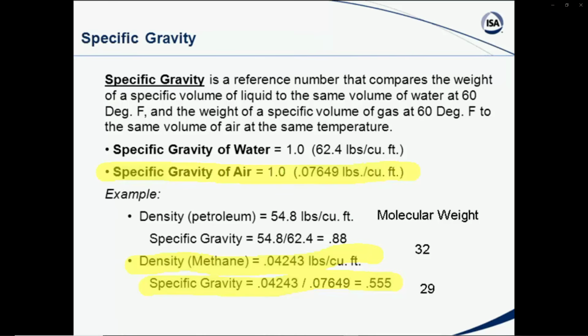It's a little bit varied from that, but in this case you would divide the 32 by the 29. In other words, you would divide the molecular weight of your gas by the molecular weight of air. And in this particular case, I don't have my calculator right in front of me, but I believe this will give you something like 1.1 for the specific gravity for that particular gas.